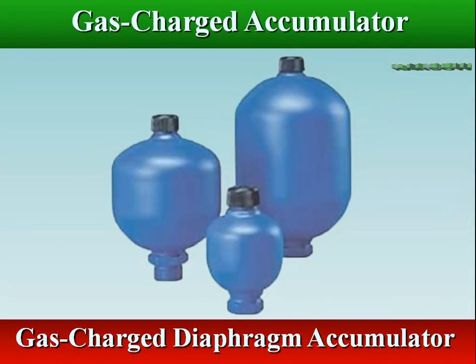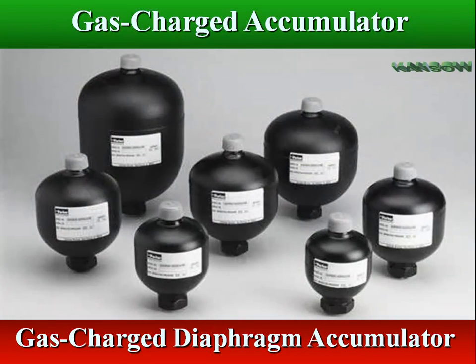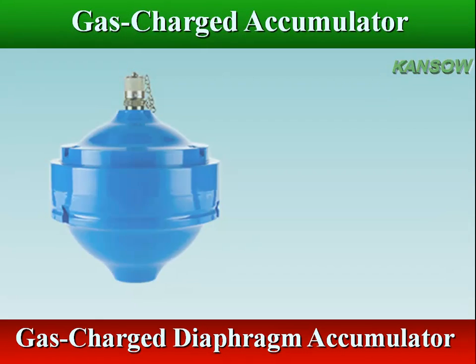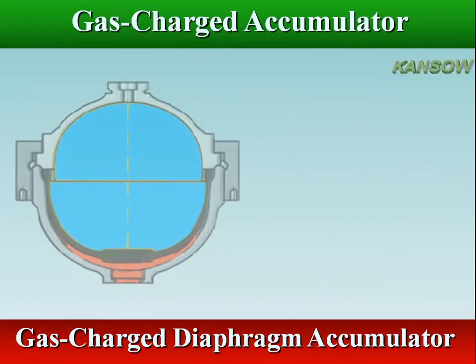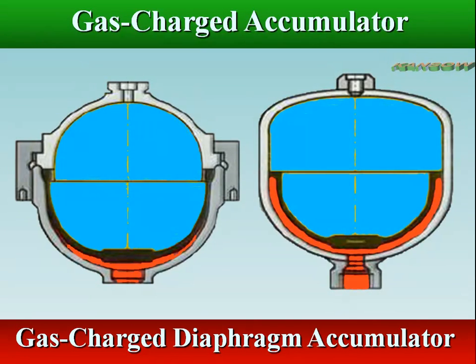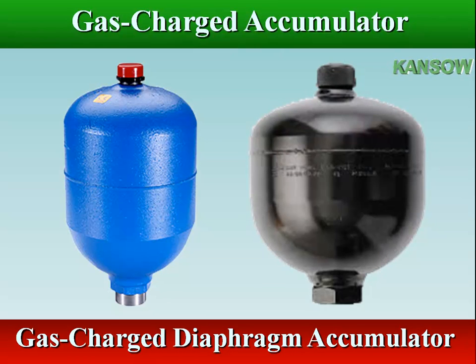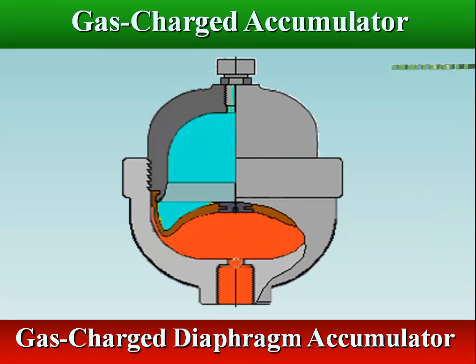Diaphragm type accumulator is similar to bladder type, except an elastomeric diaphragm is used in place of a bag. This would typically reduce the usable volume of the accumulator, so the diaphragm accumulator may not have the volume capacity of a bladder accumulator. Diaphragm accumulators may be spherical or cylindrical. The main difference with bladder accumulator is an increased maximum compression ratio of approximately 8 to 1. It is low weight, compact design, and good for shock applications with good response characteristics.